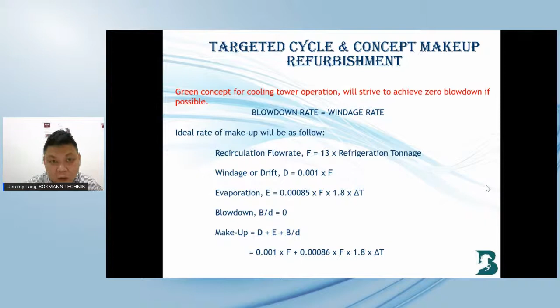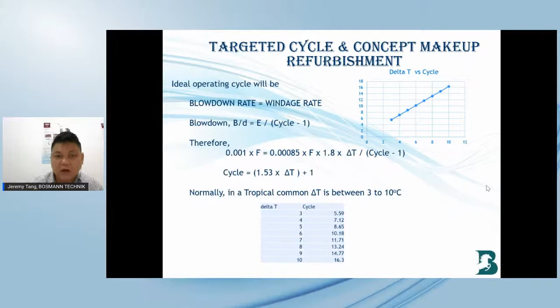So how can we do that? Let's say the delta T requirement from the customer is 4 degrees Celsius. We tabulate this into the formulation, and we can only run at the 7th cycle. Mostly the customer can compensate with a delta T of 10 degrees Celsius, so the cooling tower can run up to the 16th cycle of concentration.